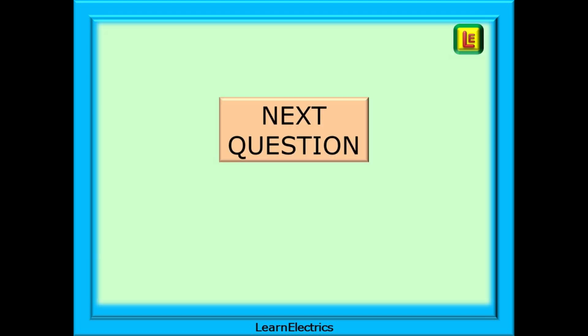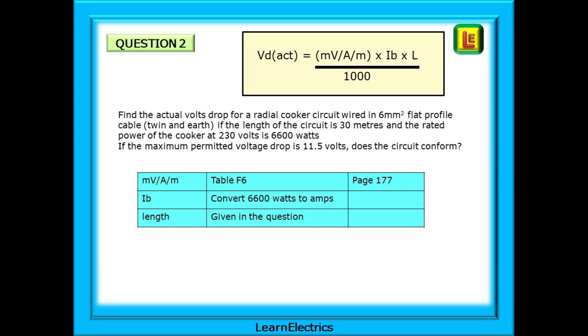Next question then and this time we will need to find the amps from the watts. Here's the question. Find the actual volts drop for a radial cooker circuit wired in 6mm flat profile cable twin and earth if the length of the circuit is 30 meters and the rated power of the cooker at 230 volts is 6600 watts. If the maximum permitted voltage drop is 11.5 volts does the circuit conform to the regulations?